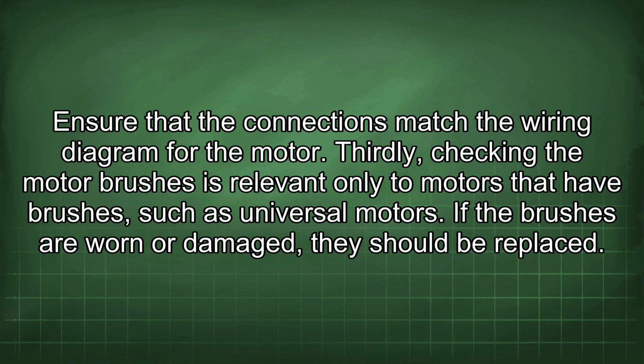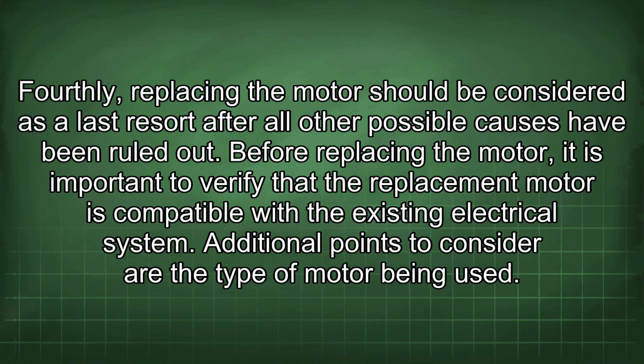Ensure that the connections match the wiring diagram for the motor. Thirdly, checking the motor brushes is relevant only to motors that have brushes, such as universal motors. If the brushes are worn or damaged, they should be replaced. Fourthly, replacing the motor should be considered as a last resort after all other possible causes have been ruled out. Before replacing the motor, it is important to verify that the replacement motor is compatible with the existing electrical system.